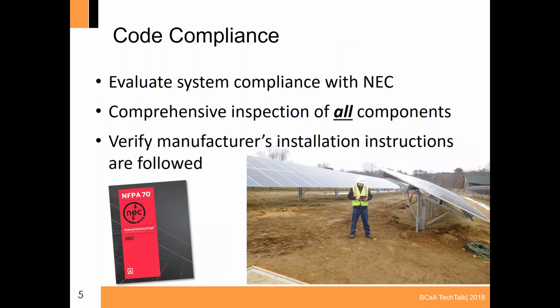Basically what we're doing is, this is more of the inspection aspect. So very similar to what the electrical inspector would do as well. We're going to typically be a lot more thorough with that, really open up every enclosure, look at every single part of the system. But we want to make sure that every aspect is in compliance with the National Electrical Code. And each state has their own adoption. Several states are on the 2017 edition of the Electrical Code. Others are on the 2014 edition, and other states might be on an even earlier edition.